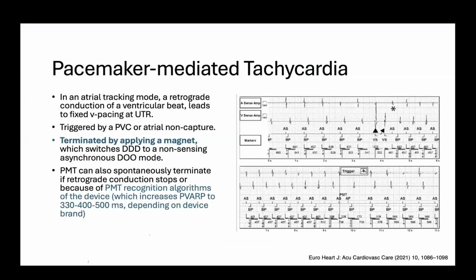So this typically happens in an atrial tracking mode where a PVC or a ventricular beat is retrogradely conducted, and this is triggered on the A and leads to a fixed ventricular pacing at the upper tracking rate. Typically, either an atrial non-capture or a PVC would trigger this, and in general, applying a magnet will terminate the pacemaker-mediated tachycardia, which switches the DDD to a non-sensing DOO mode, and that way it will terminate.